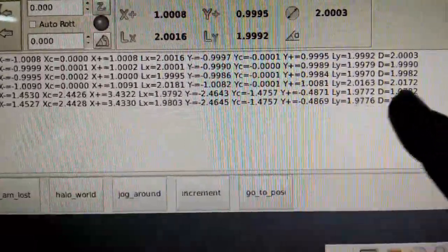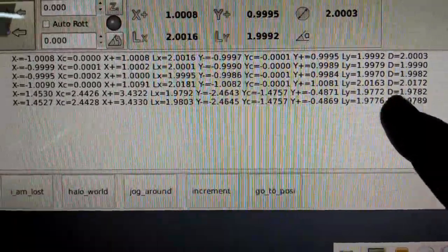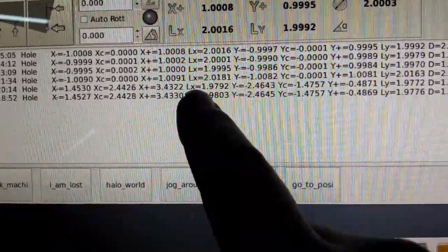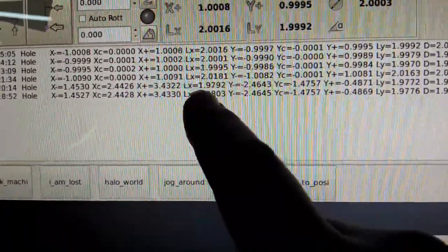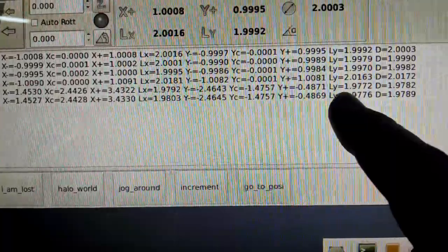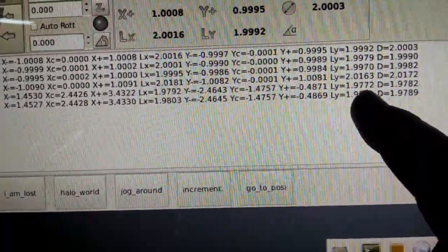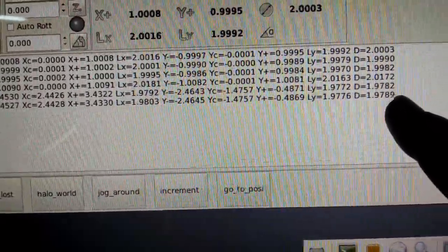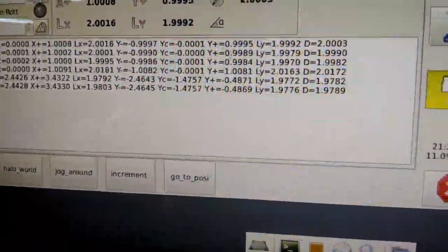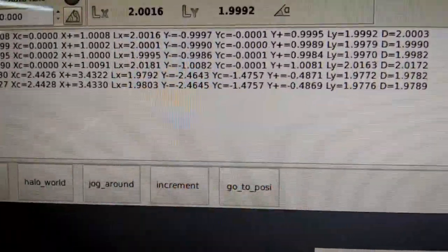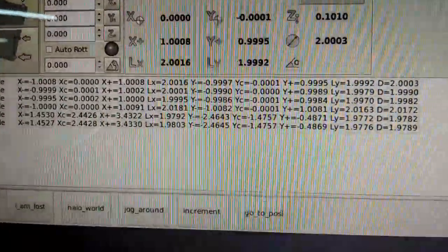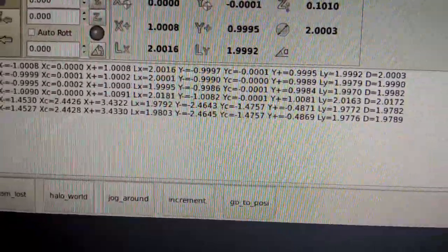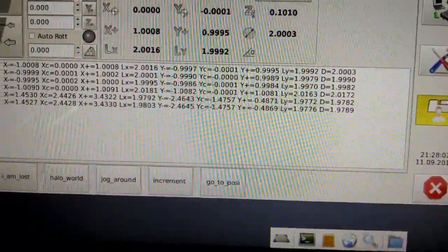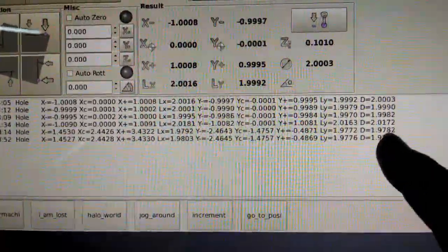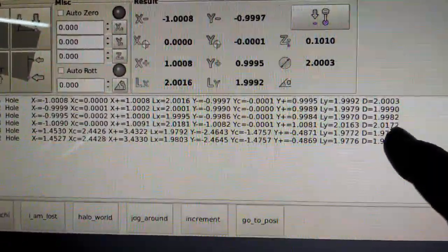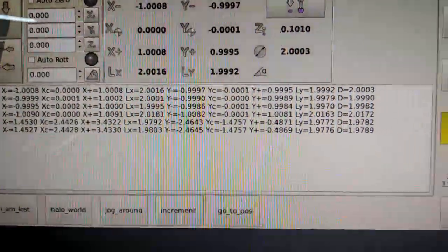So you can see this first couple was right close to the same repeatability. LX is 1.98 for both. LY is 1.977 for both. And D was 1.978 for both. So you can see that it's pretty repeatable on that. That was with a tip diameter of 0.05. Then I changed the tip diameter to the actual measured dimension of the tip, which was 0.089. So then I put that in, and you can see on the third try, the diameter is bigger than 2 inches by 17 thousandths.